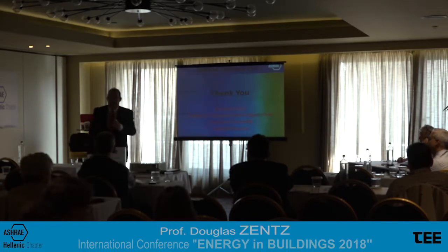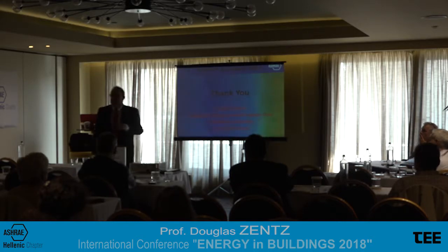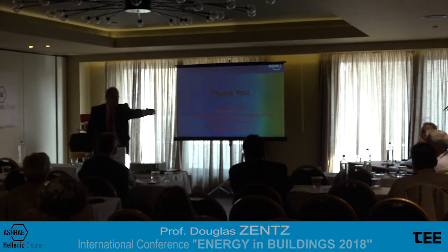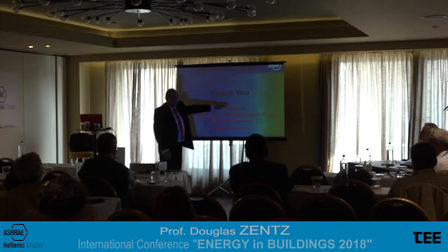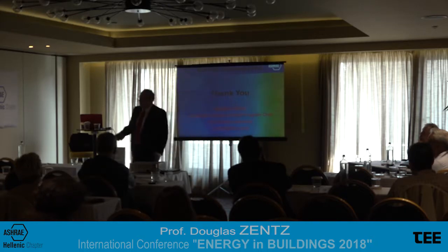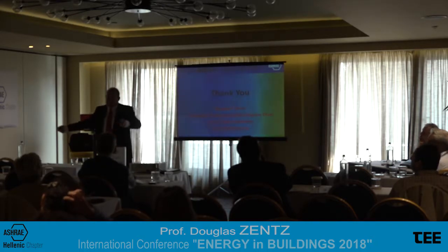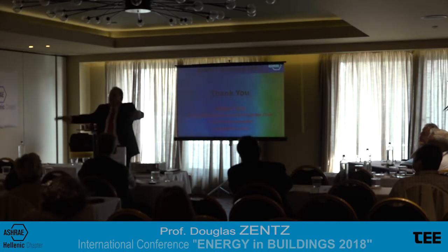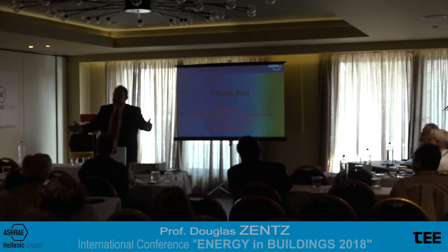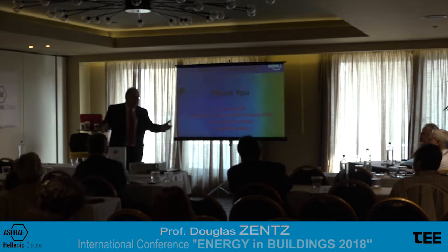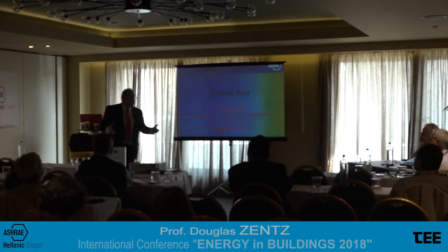20% is a big number, regardless of the use of the building. I'm giving you typical numbers, round, it varies. What we tend to do in our industry is underestimate plug load. And so that answers your question. We're supposed to be a B building, why is that a D building? Think about the buildings you walk into and everything that's plugged in. When everyone leaves, do they turn all those things off? Typically, no. They're running. It's called parasitic load. Parasitic load is very high, typically, in most buildings.